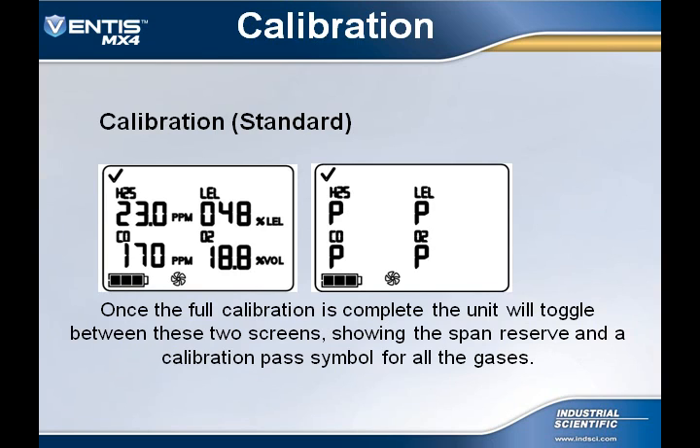Once the full calibration is completed, the Ventis MX4's display will toggle between all sensor span reserves and a P for pass or an F for failure for each individual sensor.